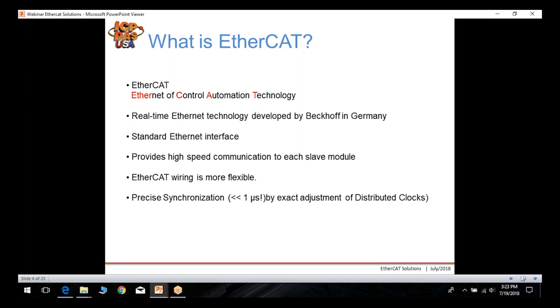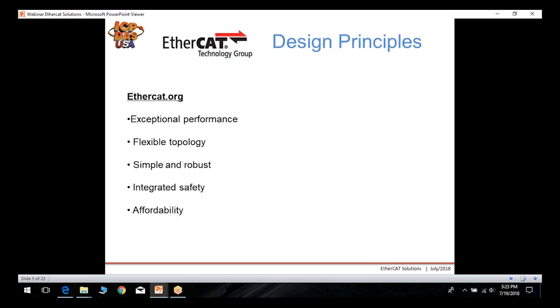What is EtherCAT? EtherCAT stands for Ethernet for Control Automation Technology. It is a real-time Ethernet technology developed by Beckhoff in Germany. It uses standard Ethernet interfaces, provides high-speed communication to each slave device, and EtherCAT wiring is very flexible. It has precise synchronization of less than one microsecond.